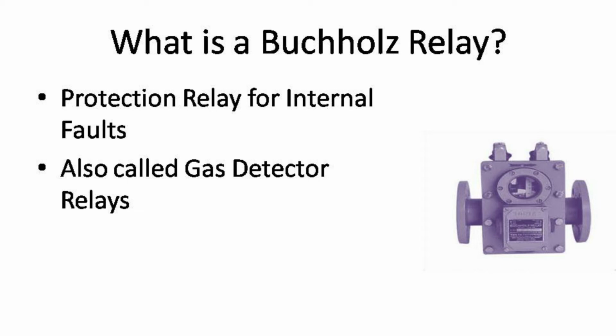With these types of relays, float switches are used to initiate an alarm when a certain oil level is detected. There are a lot of causes of internal faults within the transformer, such as bad contacts, oil leaks, ingress of air, and winding overheating, etc., which may cause the oil level to rise, and that is the reason why you need to use these types of relays.